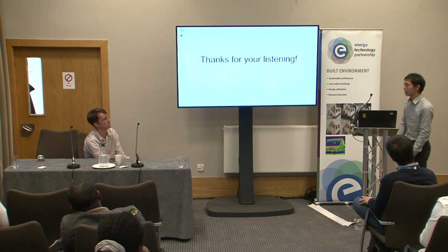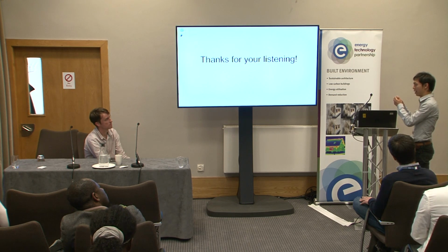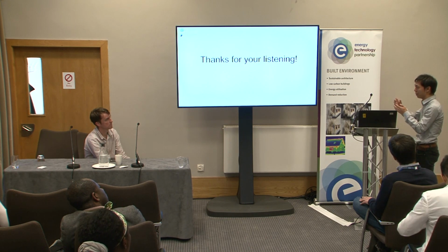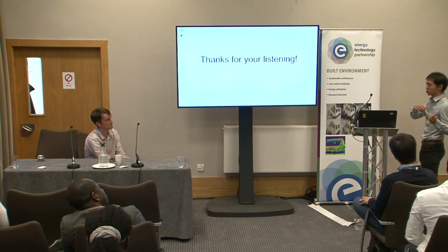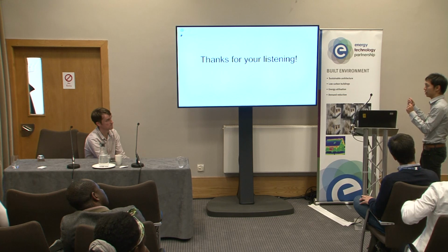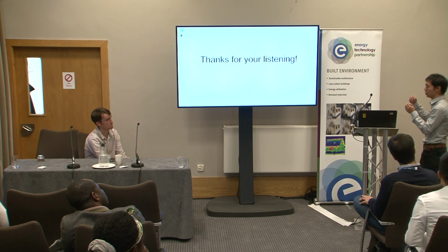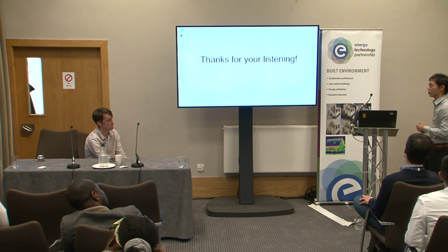What's the next steps? Yeah, next step actually, we have to combine the HEM model and AM model. Actually, AM model is an agent of HEM model. The AM model can predict the temperature and RH inside the box, and based on this model, we also need to create an energy consumption model for the precision air conditioning system. Combining these two, we have to design a control logic to search for optimal control accuracy for the room, because the energy consumption depends on control accuracy.